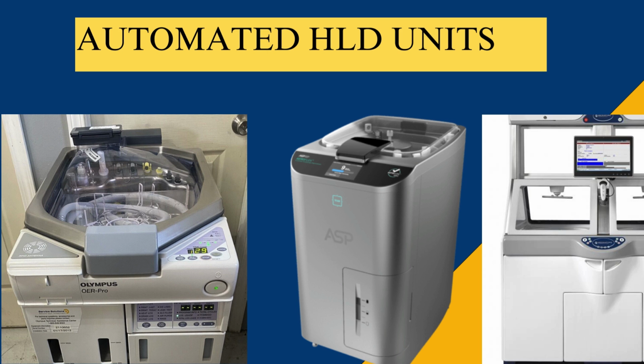Automated with high-level disinfection. Again, disinfection used to be a manual tub that we submerge our items in there, place a timer in there, wait 12 minutes or whatever disinfection you're using. With automated technology, now we have a printout of how long it's going to take to disinfect that item. There's going to be a consistent flow of disinfection within the lumens of those items. There's going to be a timer in there that lets you know if it failed or didn't fail, and a testing unit in there that allows us to tell if the disinfectant is reusable or is at the end of its life.